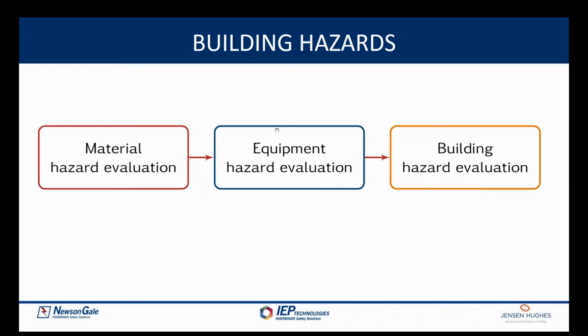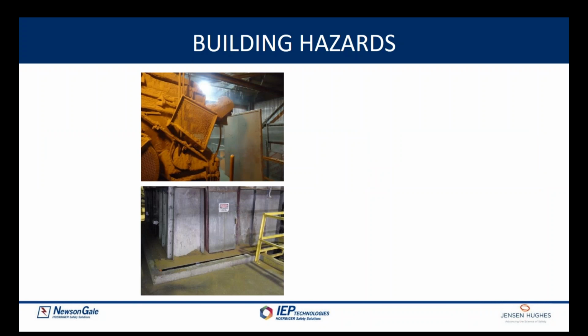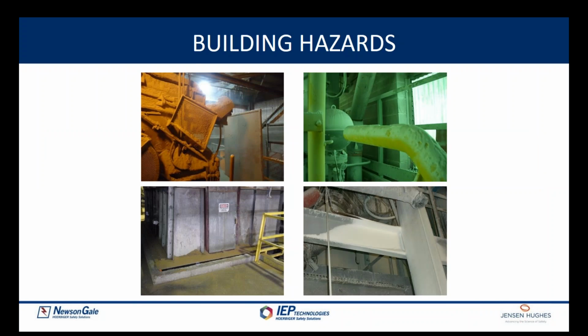The last, but arguably the most important part of a DHA is to evaluate whether or not there is potential for a flash fire or explosion in the building. Although it's arguably the most important part of a DHA, it's the simplest to address and the simplest to identify. If you walk through your facility and you cannot discern the surface color underneath a layer of dust, or if you can write your name in the dust, this is a strong indication that further evaluations are needed to characterize whether that fugitive dust accumulation is hazardous and poses a flash fire or explosion hazard.